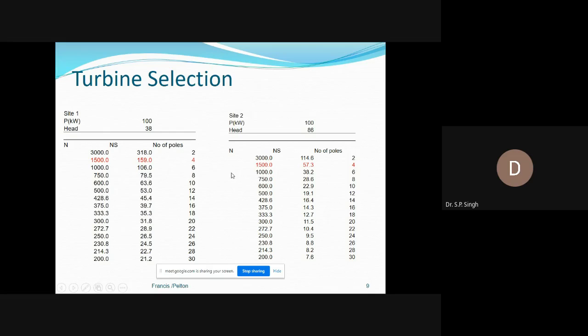This is the medium head site, and let me have a look at a higher head site. Here the head is high, say 86 meters, and the specific speed comes out to be 57.3. Suppose I select a speed of 1500 RPM, so the number of poles of a synchronous machine, or any machine, may be 4 poles. This is acceptable, no problem. The problem comes when the head becomes very low.